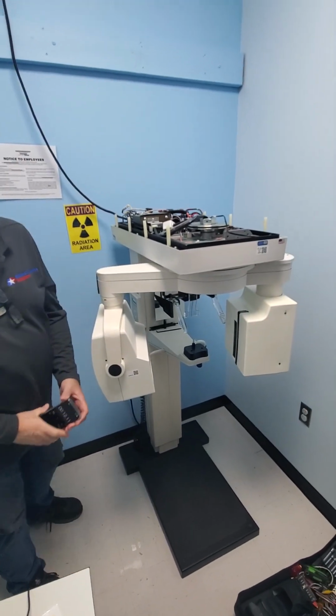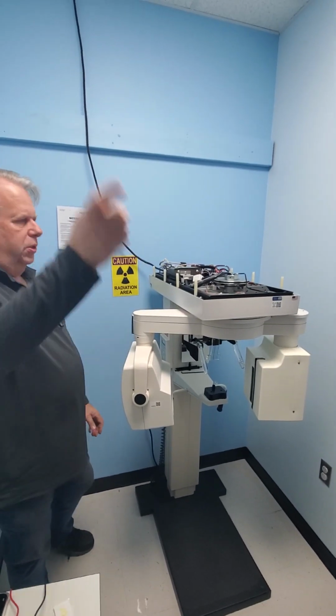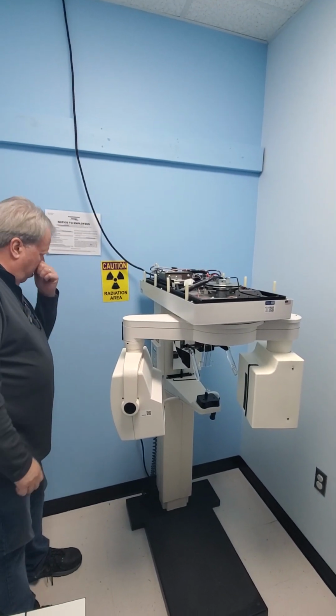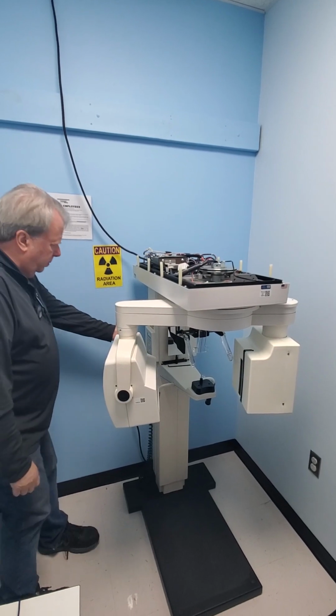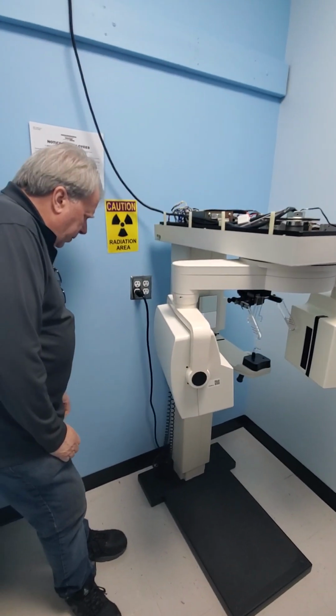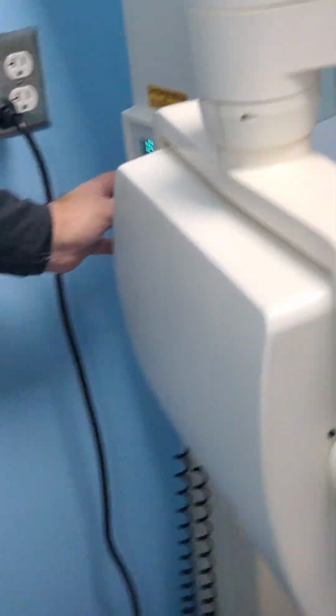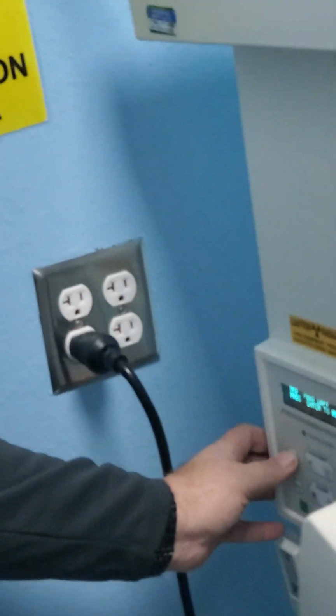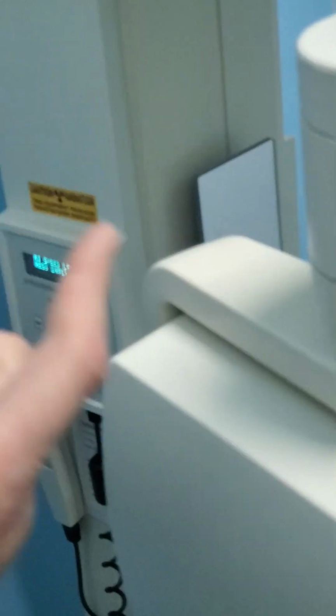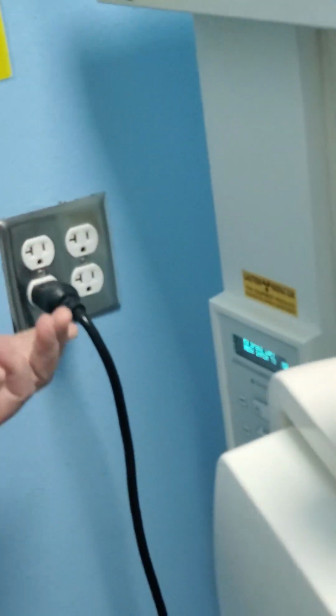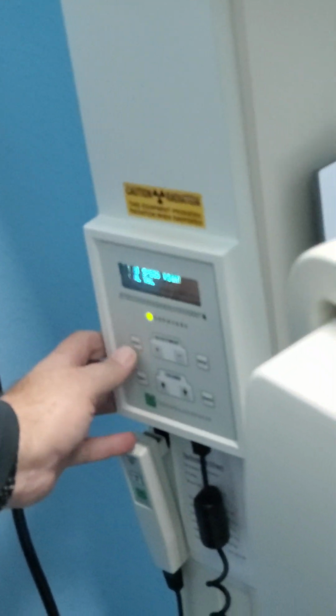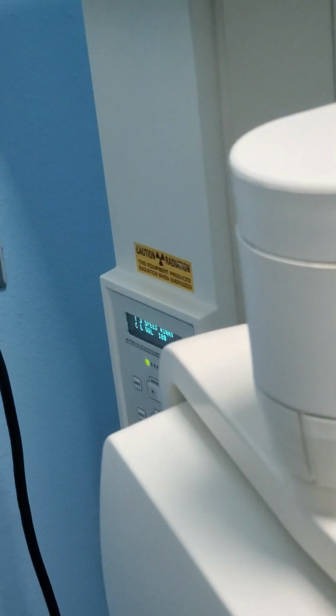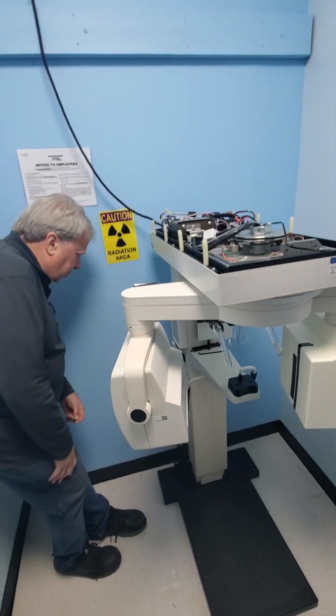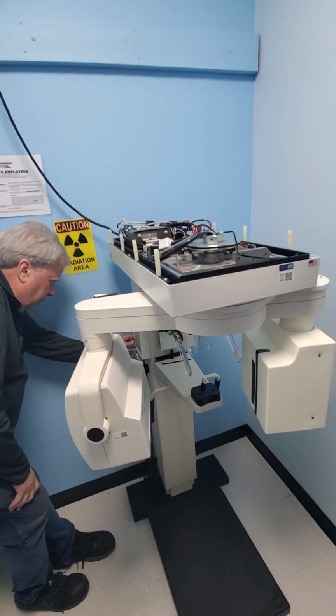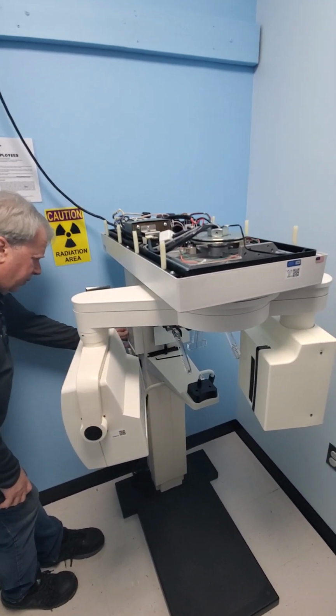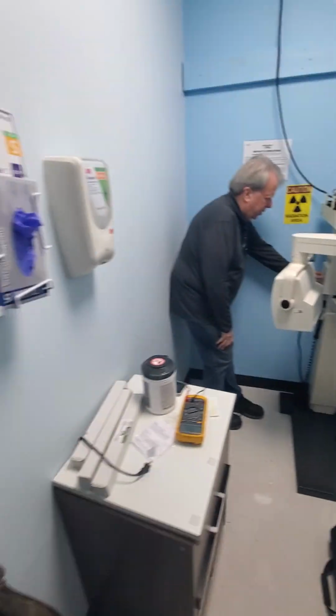I think there'll be a more accurate way when we do the calibration to determine what the exposure time is. Okay. So that's exposure time. It has a pan speed left, pan speed right, TMJ speed left, TMJ speed right, and I just do the pan speed in the direction that they use it. Don't worry about the TMJ speed. Yeah, don't worry about that. Exposure count, if you're interested, is 6,088.